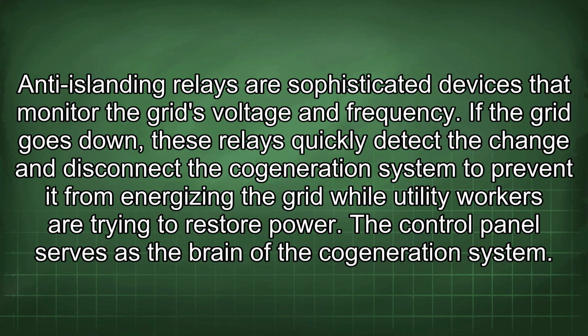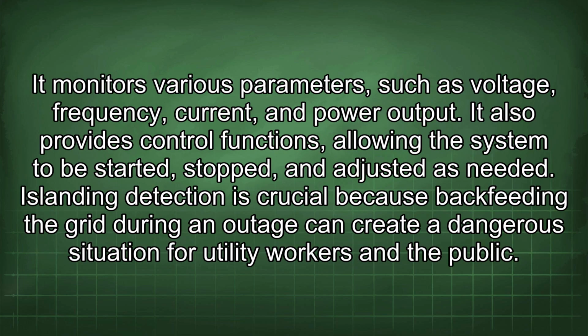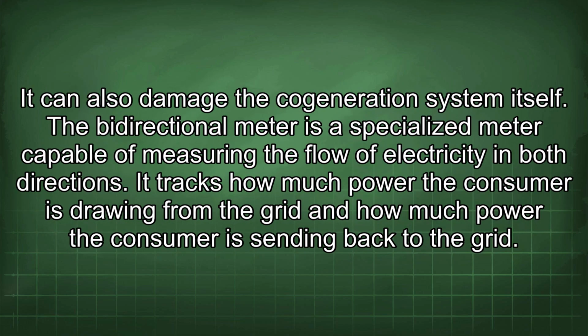The control panel serves as the brain of the cogeneration system. It monitors various parameters, such as voltage, frequency, current, and power output. It also provides control functions, allowing the system to be started, stopped, and adjusted as needed. Islanding detection is crucial because backfeeding the grid during an outage can create a dangerous situation for utility workers and the public. It can also damage the cogeneration system itself.